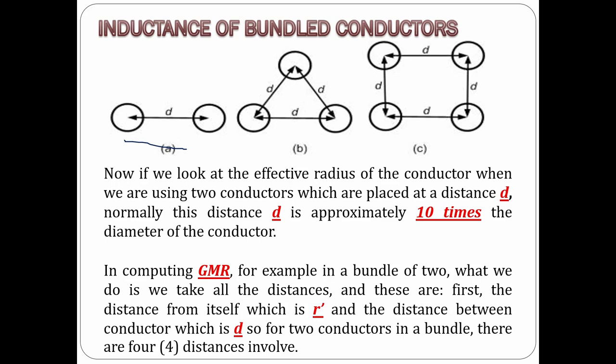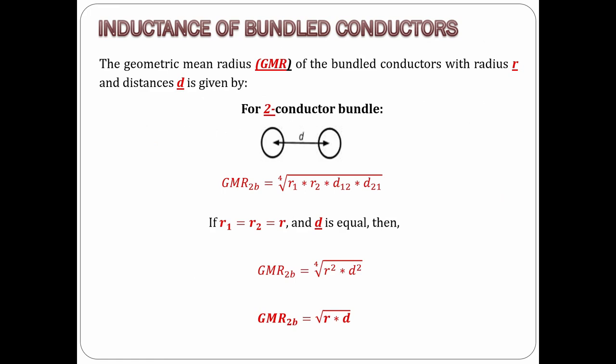In computing the inductance of bundled conductors, we need to first determine the effective radius, or geometric mean radius (GMR), of the bundled conductors. For two bundled conductors, the formula uses r as the radius and d as the distance between conductors. The number of terms comes from squaring the number of conductors — so for two conductors it is two squared, which is four. The root is also four. The first two terms are the radii r1 and r2, and the last two terms are the distances d12 and d21.